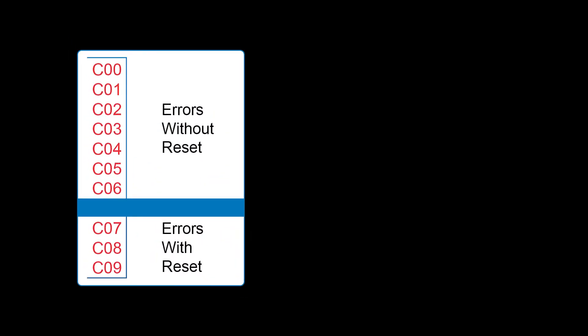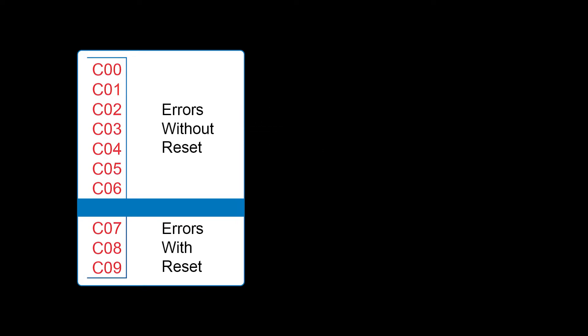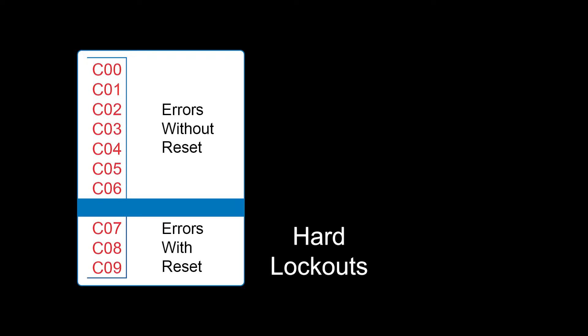C00 through C06 are what we call anomaly codes. These will not register on the front display and do not require a soft lockout or a hard reset. C07 through C09 are your hard lockout errors — those are the ones that require a reset button to be pressed.